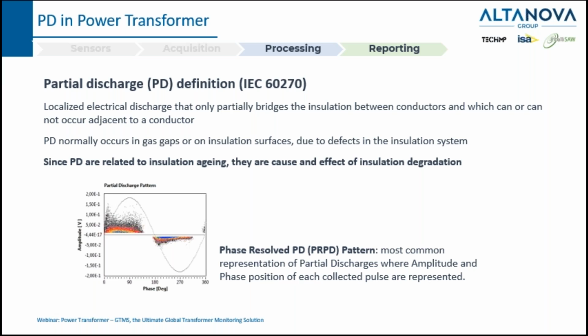Regarding PD, let me take a step back to the definition of partial discharge according to IEC standard 60270. Basically, PD is a localized electrical discharge that only partially bridges the insulation between conductors, and normally partial discharge occurs in gas gaps in a transformer, for example, or on insulation surfaces. One important thing to highlight is that since partial discharges are related to the aging of the insulation, they can be an effect or a cause of the degradation of the insulation.